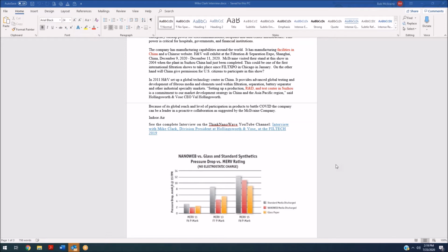Your furnace filter, for example, that may be in your home or in a commercial environment, they recommend be changed frequently because we're not sure how they're discharging. That's always a big topic of debate between the US and Europe, and how to gauge that correctly. The truth is probably somewhere in the middle. There's great value to electrostatics when you can use them. But if you need absolute filtration all the time, then there are mechanical technologies that we have that allow you to have high efficiency with a low pressure drop. So the best of both worlds, but there's always a trade-off.